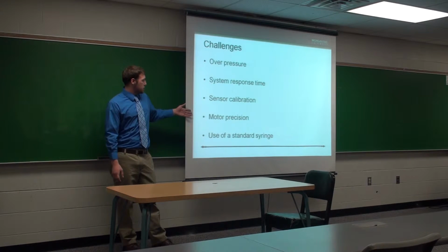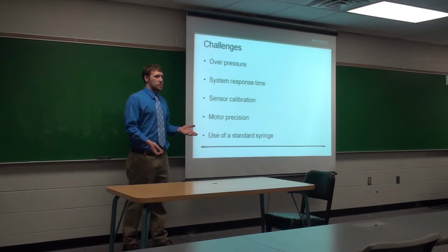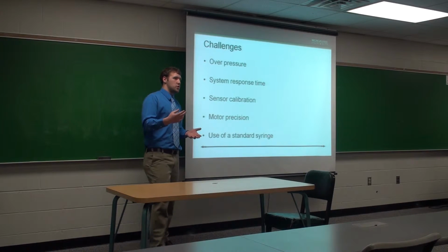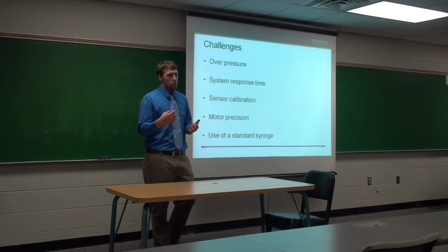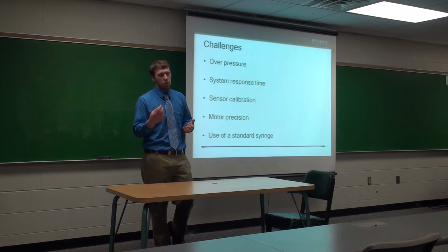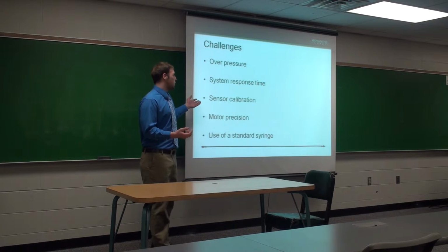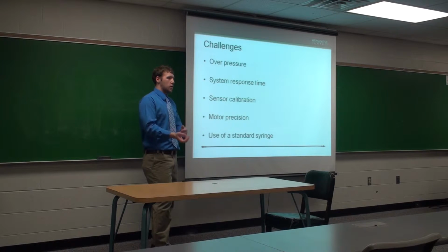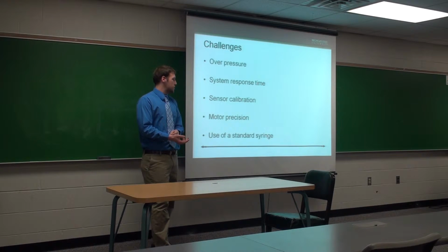Motor precision is also going to be an issue because if the step size is too large, we may be pumping too much pressure into the system, which may cause harm to the animal, which may also put us over the sensor limit, which could cause more problems with the device.